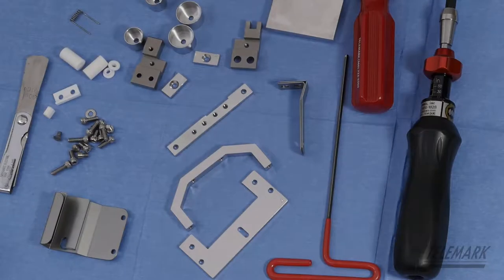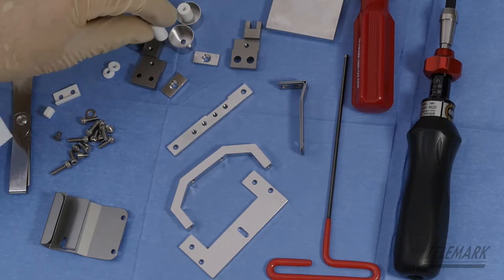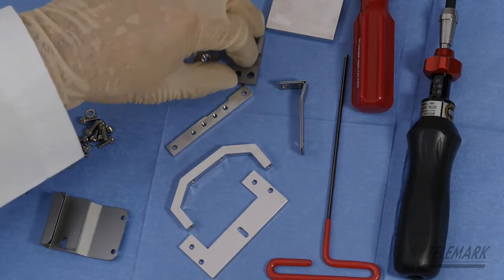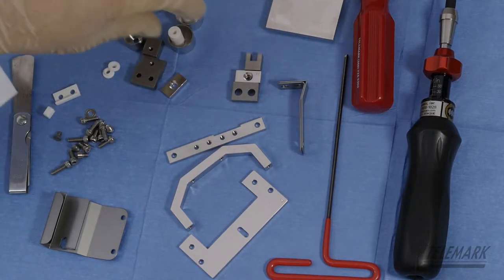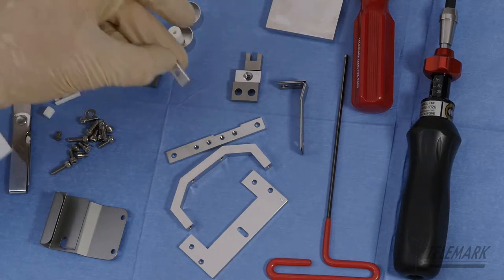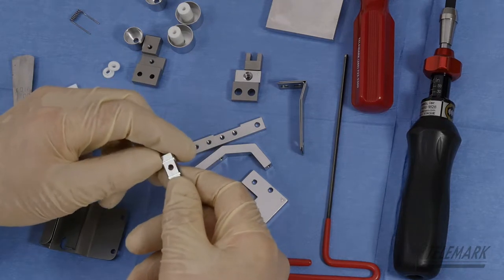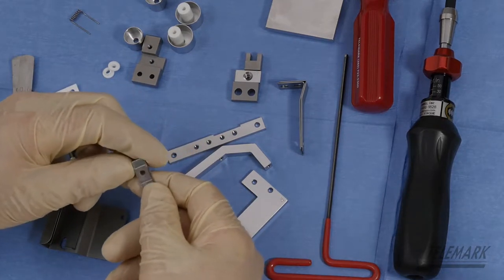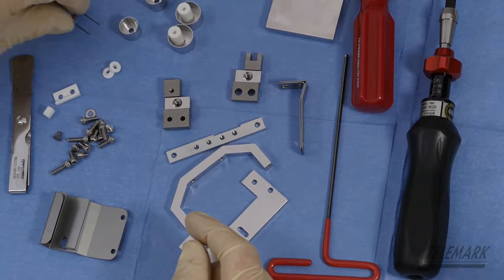Okay, this is a Telemark 274-0150-1 emitter and we will start by getting some of the subcomponents out of the way. You've got a filament clamp going into the right cathode block and a filament clamp on the left side. There's a long side and a short side to it. Put the long side because we have a seven and a half turn filament.